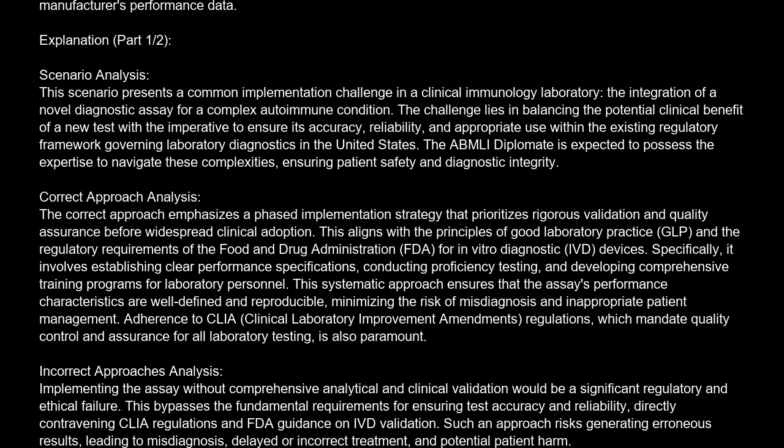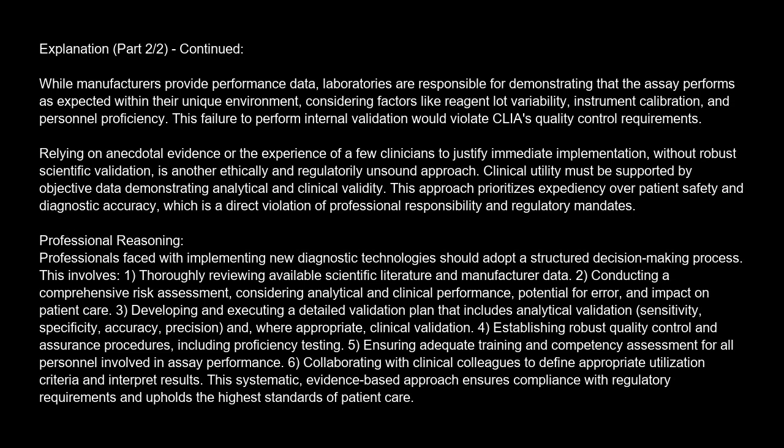Adopting the assay based solely on manufacturer claims, without independent verification of performance in the specific laboratory setting, is also professionally unacceptable. While manufacturers provide performance data, laboratories are responsible for demonstrating that the assay performs as expected within their unique environment, considering factors like reagent lot variability, instrument calibration, and personnel proficiency. This failure to perform internal validation would violate CLIA quality control requirements.